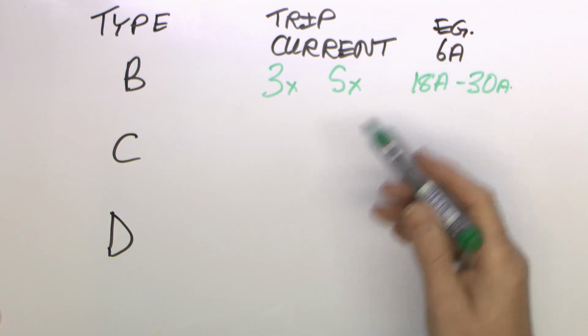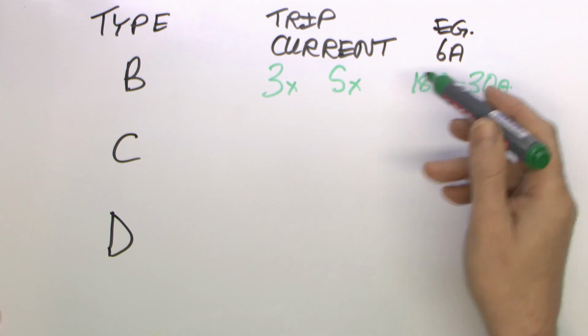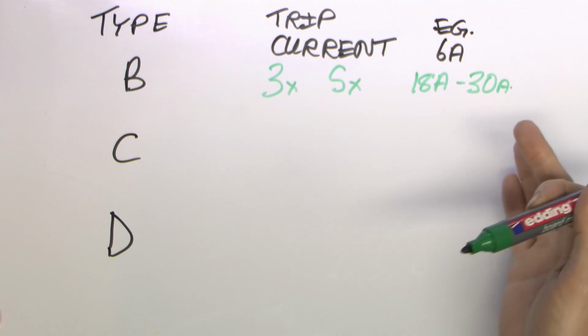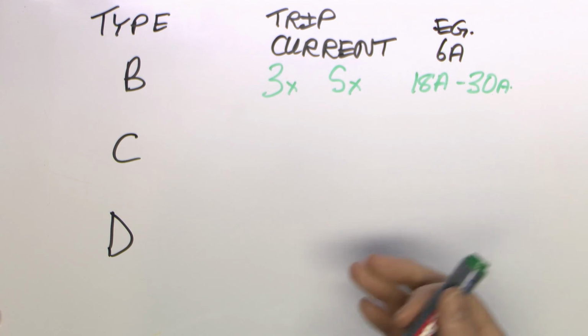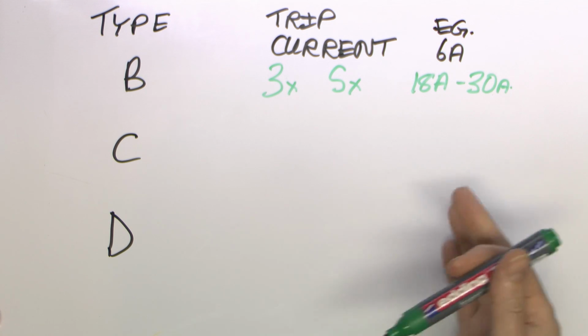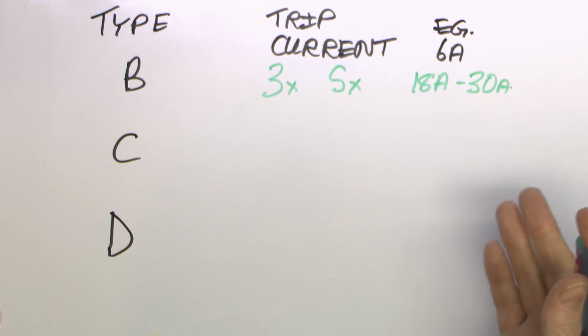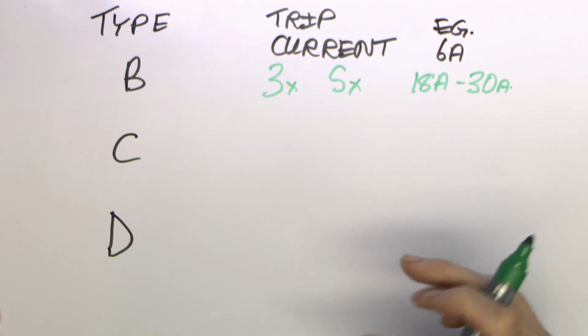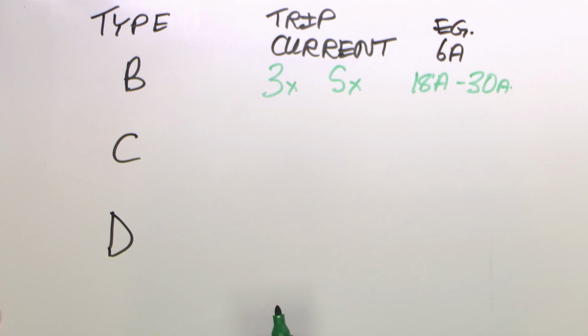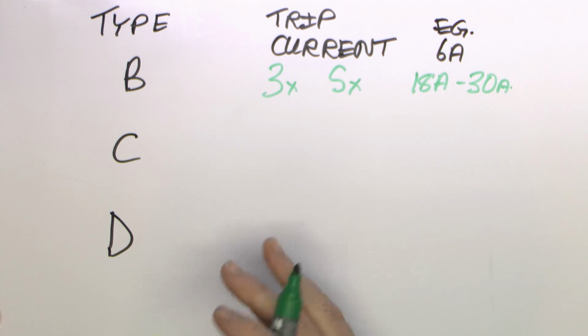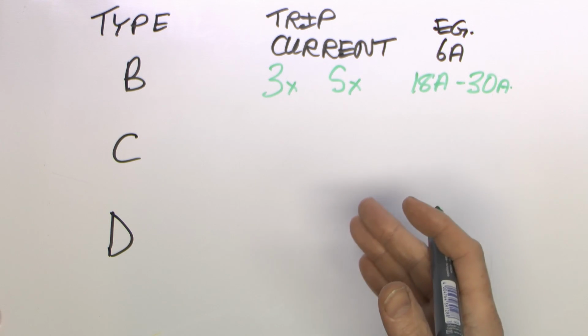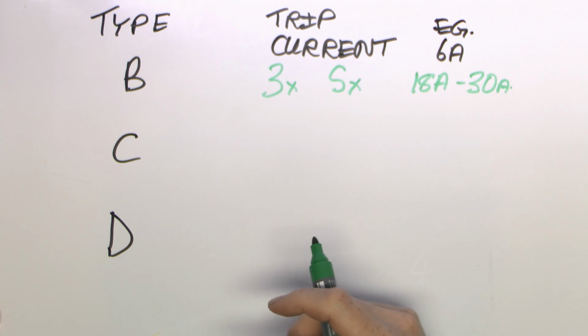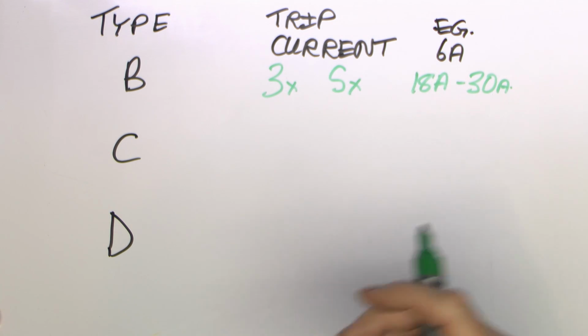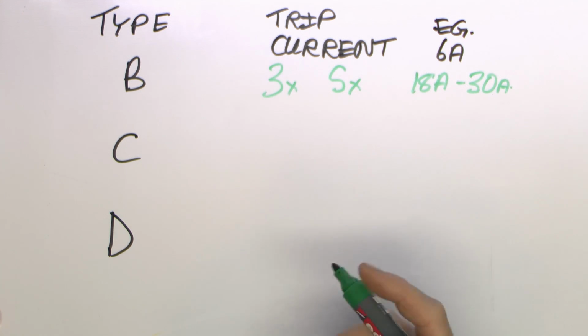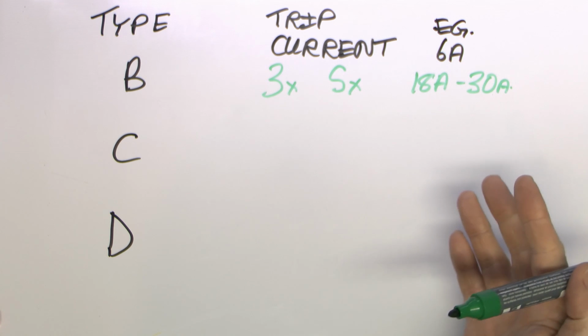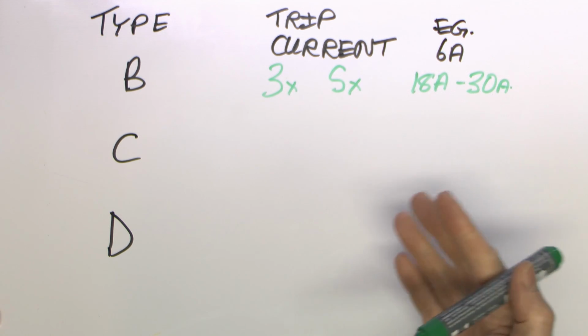And this may seem surprising, but of course this is actually an intentional design. If you had a circuit breaker which tripped at 6.1 amps instantly, it would be completely useless, because when you turn on pretty much any piece of electrical equipment, there's usually a bit of a surge initially. If this was an incandescent lamp, that's because the filament has a lower resistance when it's cold, so you get an initial burst of electricity where the current is much higher. The same thing applies to motors, because it's a magnetic device, and in the time between power being applied and the magnetic field establishing, you can get a fairly high current. And even with power supplies for computers and whatever else, when you switch it on, the capacitors inside have to charge up, and before they're charged they're presenting what's almost a short circuit to the supply, so again you get a bit of a surge when you turn those on.